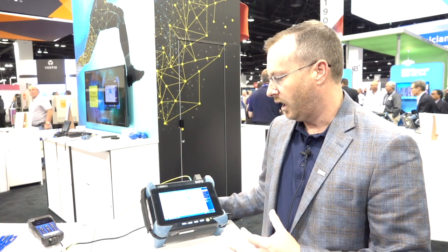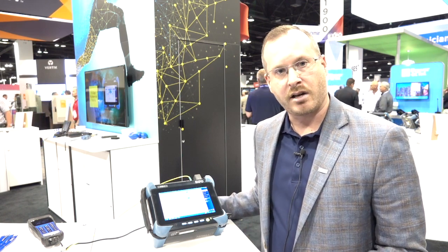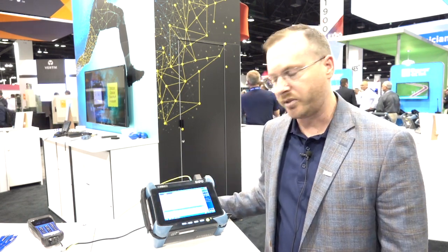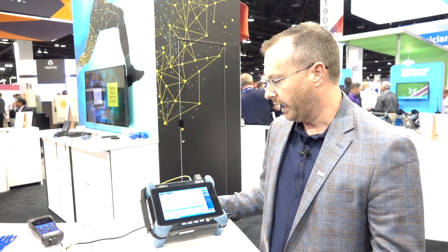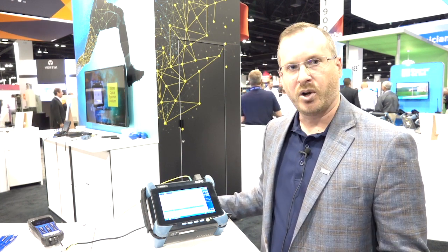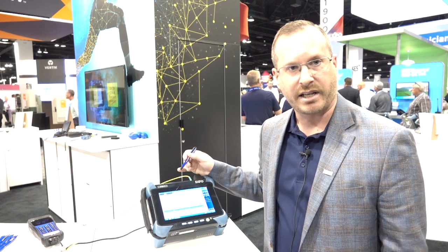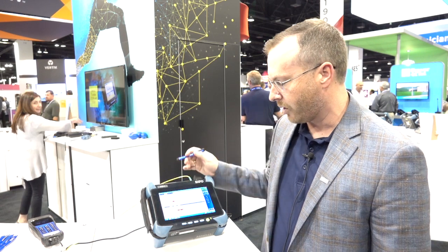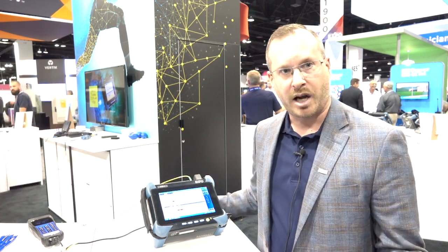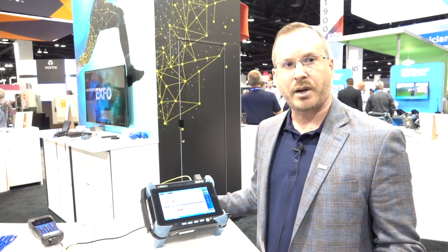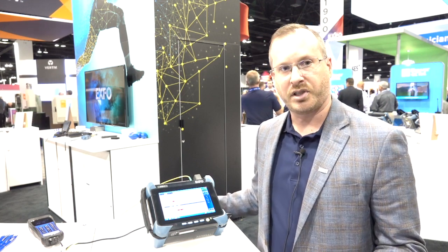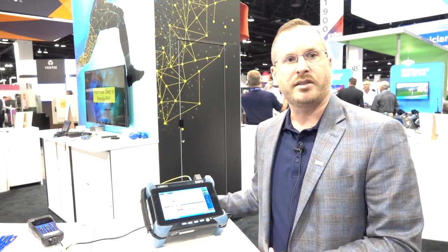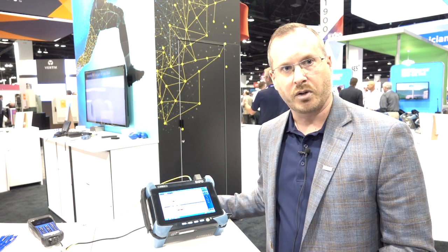So this unit here has both our OTDR and our IOLM technology. The OTDR is what everybody's familiar with, which is standard OTDR tracing. Full auto, real-time modes, standard event tables that everybody is used to, that OTDRs have been that way for many years. But then we also have our advanced IOLM, which is the Intelligent Optical Link Mapper, which is a multi-pulse acquisition test. We're going to go in and run multiple acquisitions, varying all the settings, so that we get full granularity and we eliminate the dead zones that come with testing on traditional OTDRs.